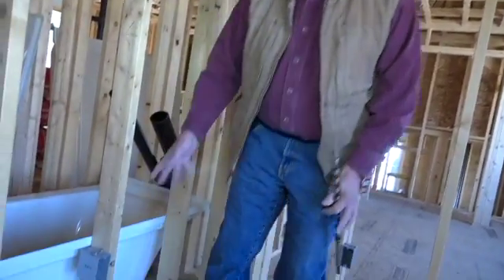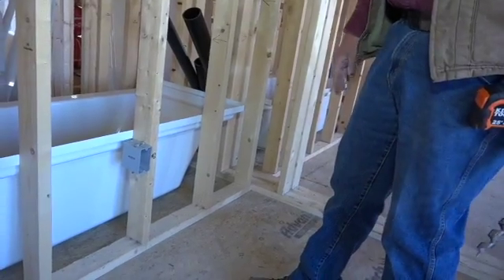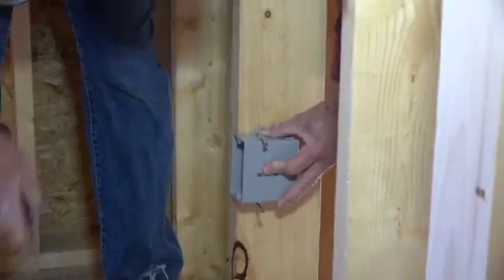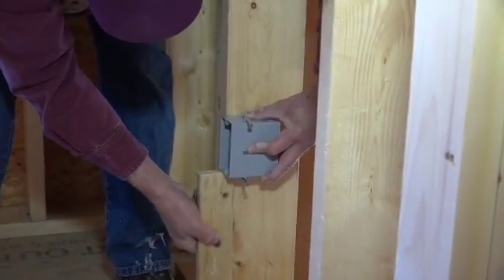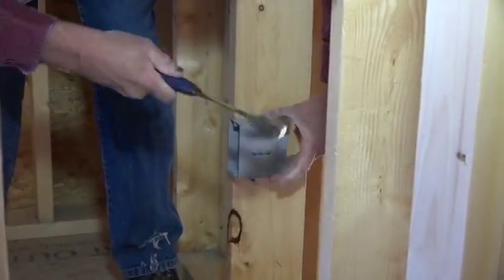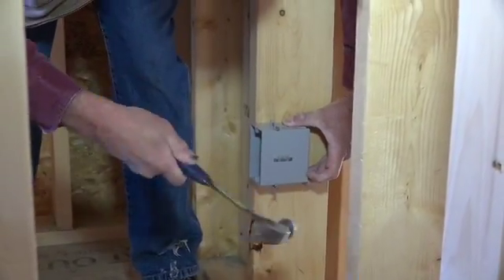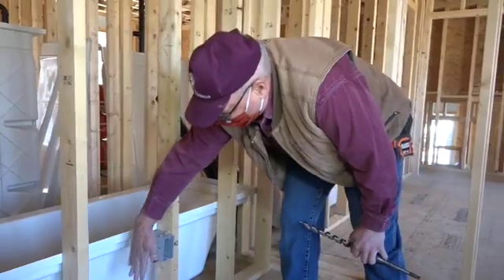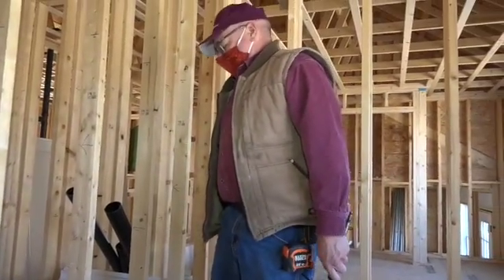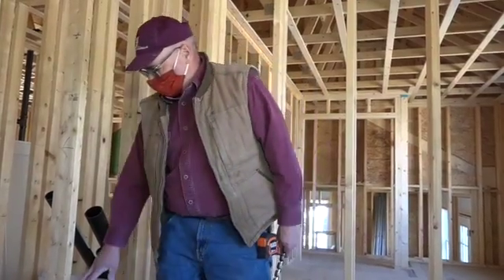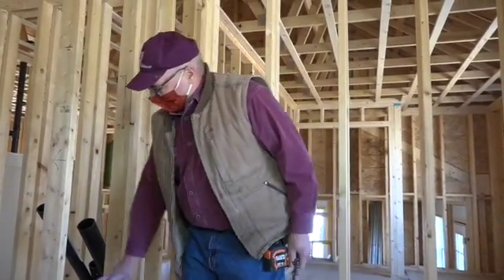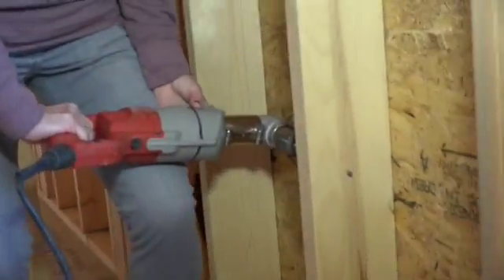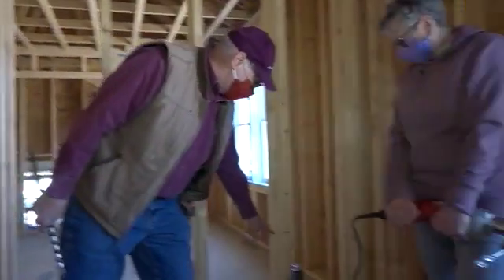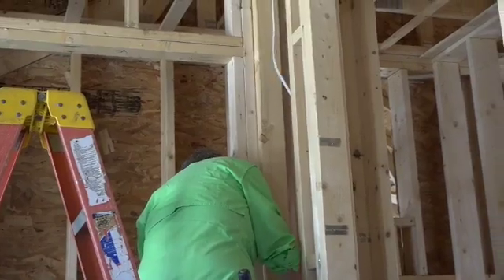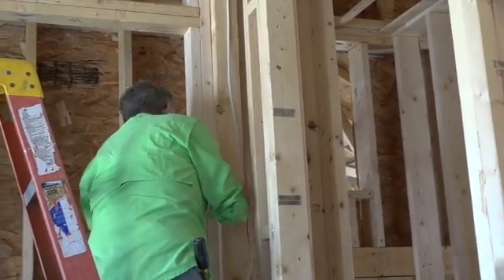The boxes are mounted approximately 15 to 16 inches off the floor on center. What we do is we cut a piece of board that is this dimension from here to here, set the box on it, and then nail the box to the side of the stud. Once all those are in place in the room, we drill holes through approximately a foot above the box. As you can see, there's one here, and that's where the wires will be pulled through the wall and into each box.